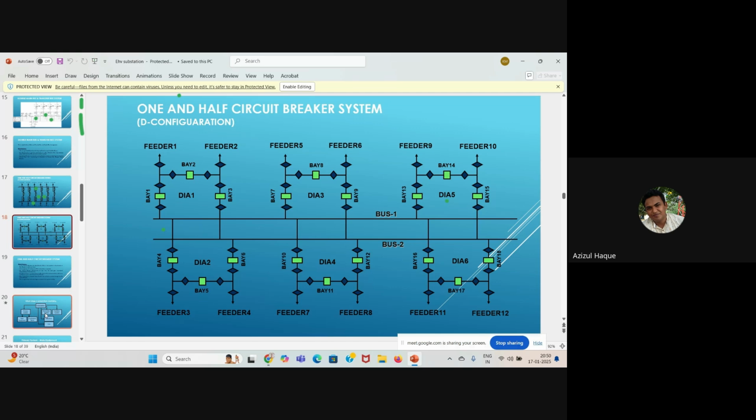Yes. Suppose this feeder 1, power is flowing to this feeder through main bus 1, and this other feeder 2, power is being fed from main bus 2. Now in that condition, let us connect this tie breaker. Suppose it is not connected, and a fault comes and both the buses get tripped.